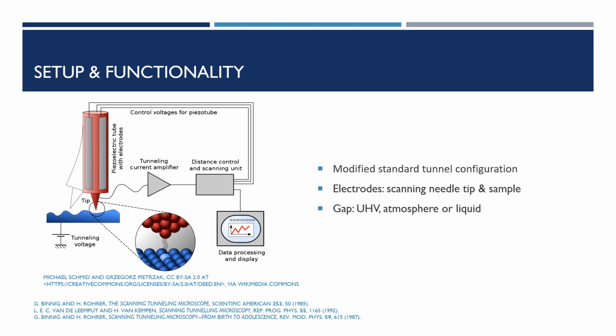Now we come to the setup and the functionality of the STM. To build the first STM, the already known standard tunnel configuration containing the two electrodes separated by an insulating layer was slightly modified. One electrode, here the blue one on the bottom, was replaced by the sample, but this also means that one surface to be investigated has to be conductive. The other surface is replaced by a very thin, at its best single atomic, scanning needle tip. The most commonly used tip materials are tungsten, platinum, or platinum iridium wires. The gap between is often empty, so ultra-high vacuum.